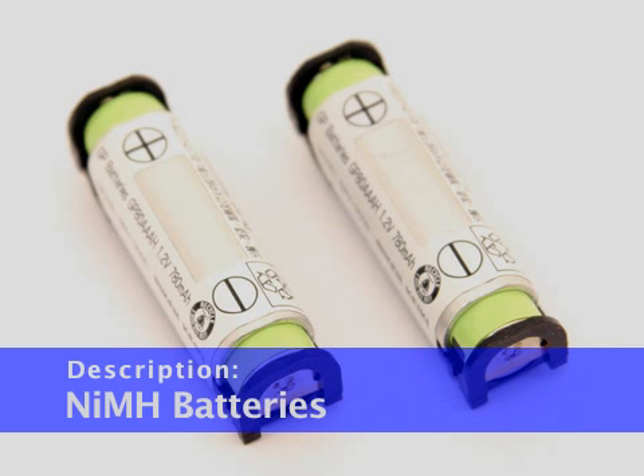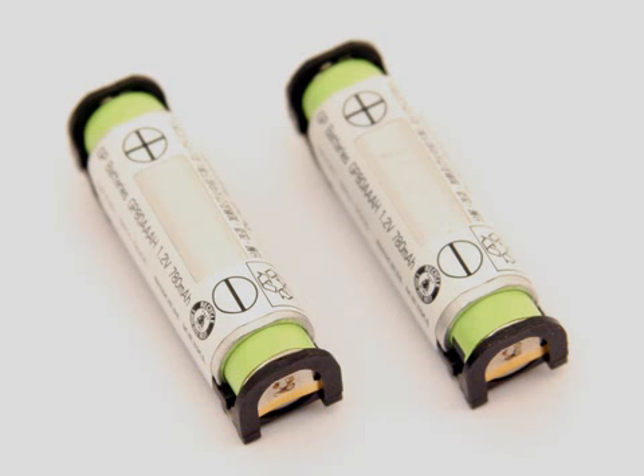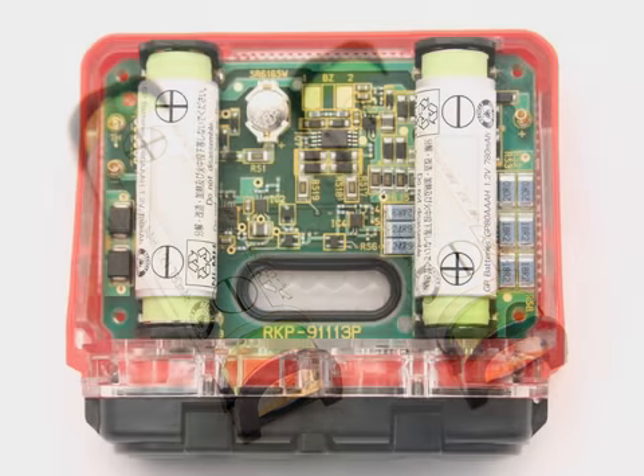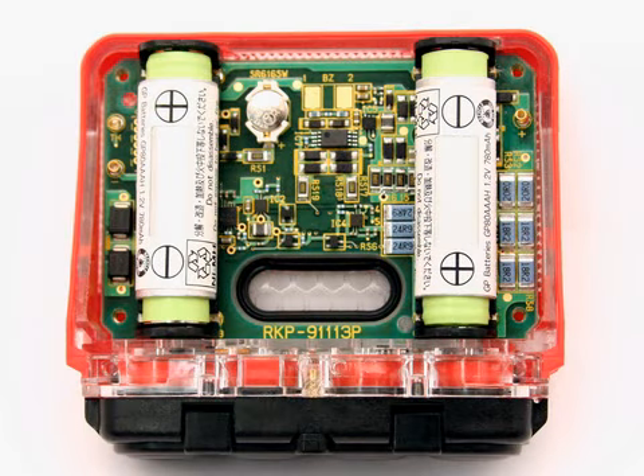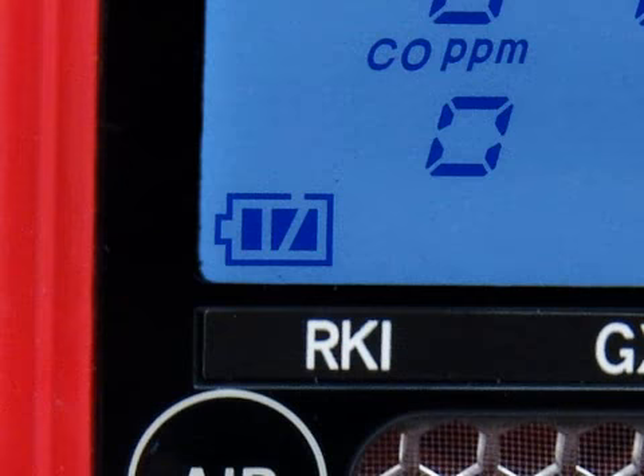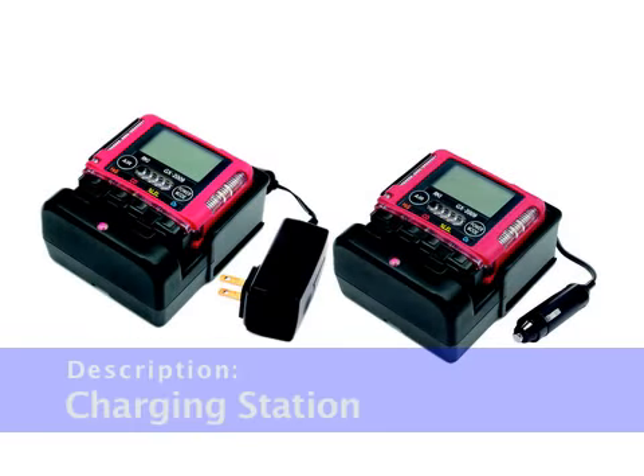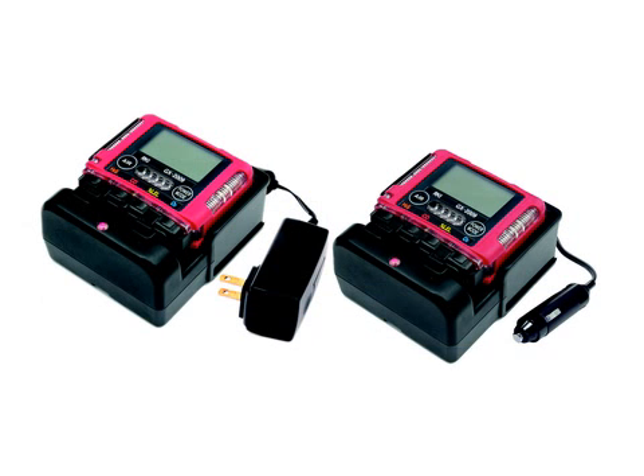The two nickel metal hydride batteries supply 2.4 volts to power the GX-2009. The batteries will run the unit for up to 20 hours when no alarms have been activated during that time period. The batteries are designed to be charged while enclosed in the GX-2009, utilizing the GX-2009 charging station. The batteries should not be removed from the GX-2009 unless they need to be replaced because they will no longer hold a charge. The battery icon in the lower left corner of the LCD shows the charge remaining in the batteries. The GX-2009's nickel metal hydride batteries are charged with the GX-2009 charging station.